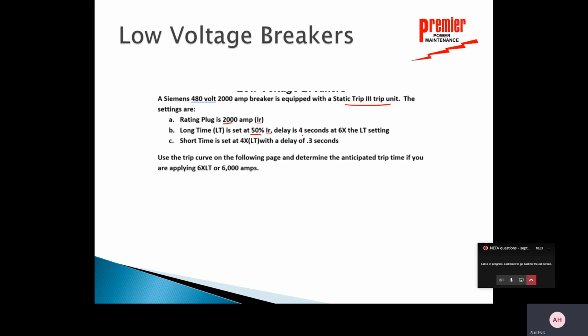Delay is 4 seconds. 4 seconds at the 6 times a rating. Okay, then item C here is the short time setting is set at 4 times the long time setting with a delay of 0.3 seconds. So question is, using the trip curve on the following page, determine the anticipated trip time you would get after applying 6 times long time pickup or 6,000 amps.